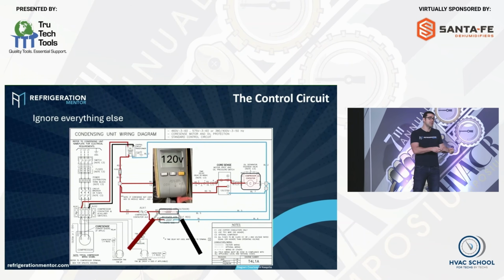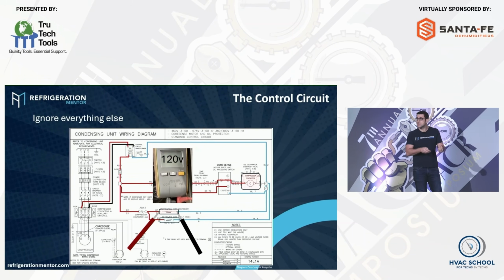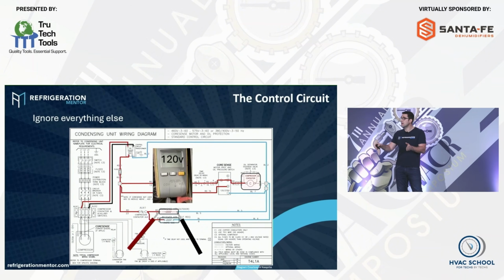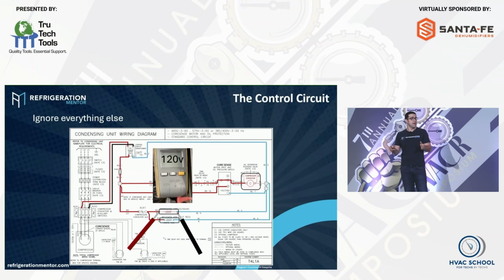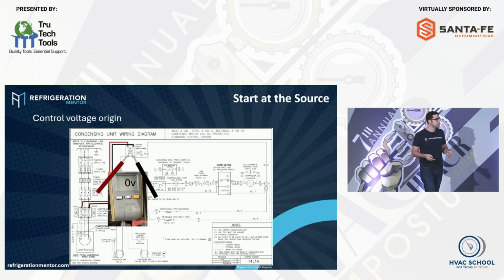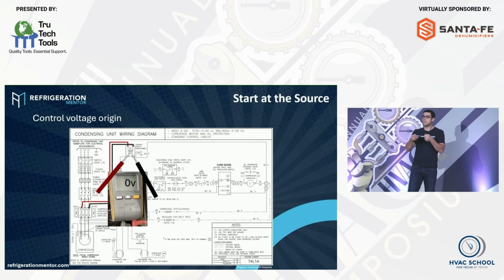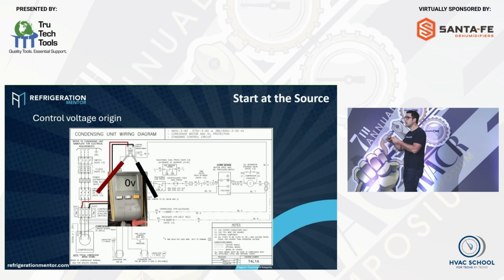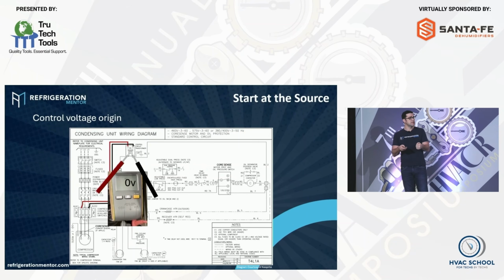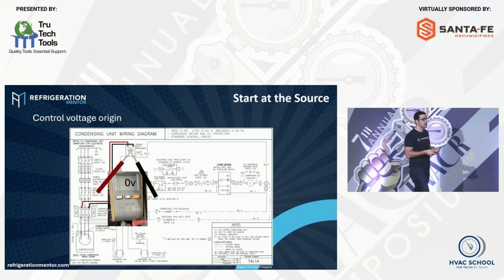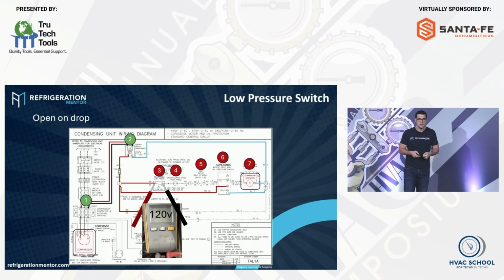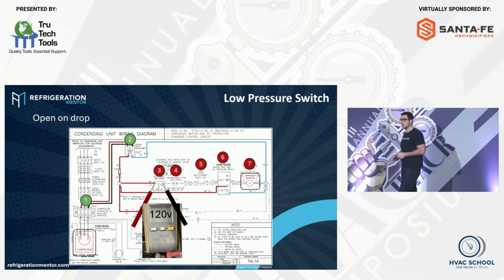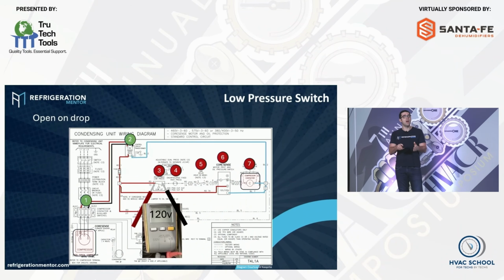You don't have to go across all the power side loads and check all that. You've got to focus on that area that has tripped. What could it be? You've got to start at the source. Where is the source? Well, I've got primary power to my transformer, and then I've got my secondary power to my transformer. Do I have voltage there or not? Okay, if I do have voltage there, what's the next step? Then we check that circuit.